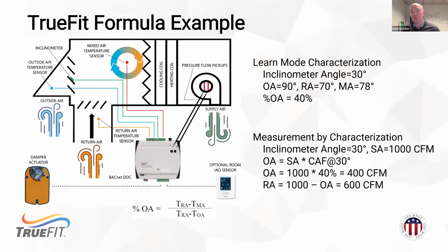Turning that around for a measurement based on the performance curve, if we're at any given inclinometer position, here we happen to be at the same one. If I have a good supply air total, I can look up with the chart to say my characterized airflow at 30 degrees position was 40%. 40% of 1,000 is 400. The balance would be coming from the return. So the same type of equation lets us profile while we're learning, and then the same math based on the performance curve gives us the measurements when we're actually reading airflow.